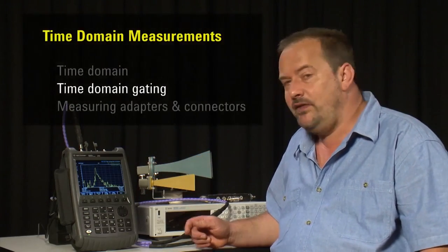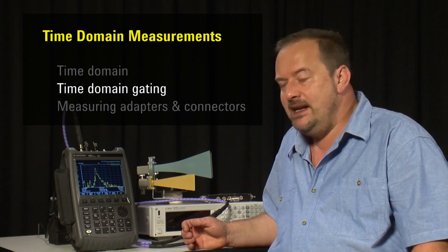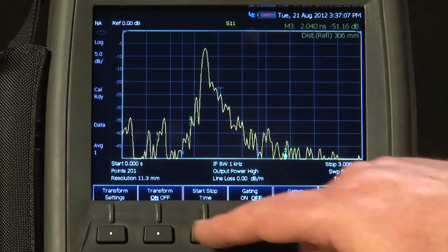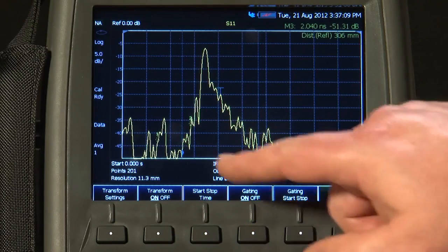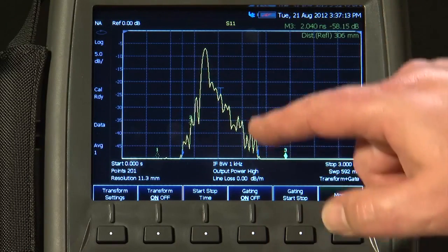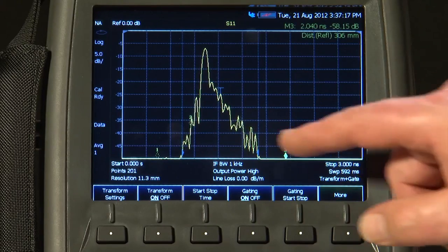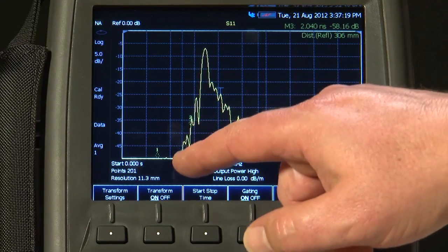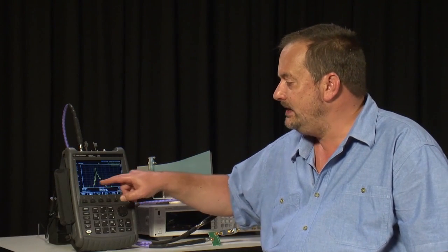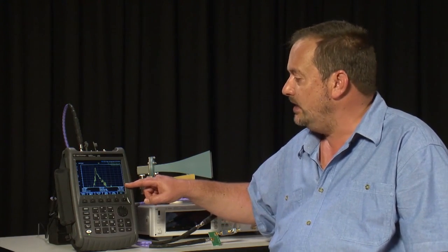But the FieldFox has an especially useful function called time domain gating. What time domain gating does, if I just turn it on, where these blue markers are, it keeps the trace. But to the left and to the right of the markers, it artificially sets the trace data to zero. In other words, it has deleted from the time domain response the non-50 ohm discontinuity effects that we do not want to measure when we are measuring S11.